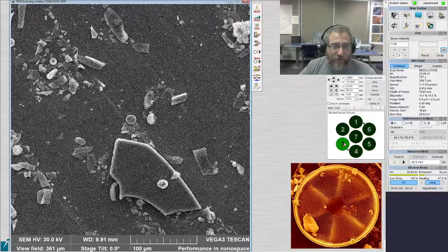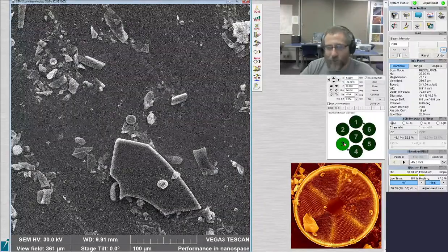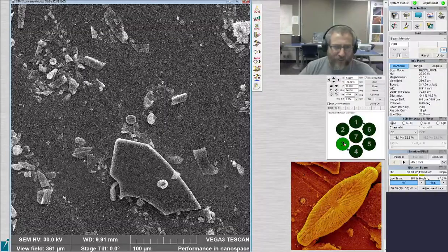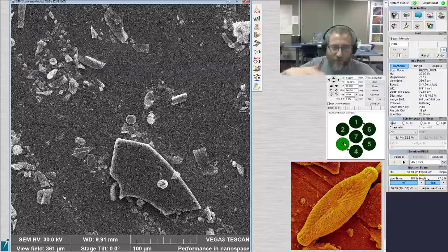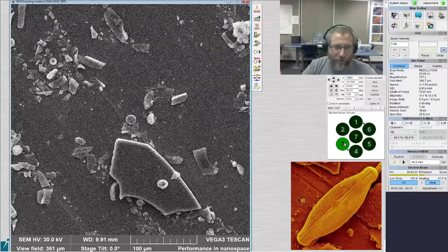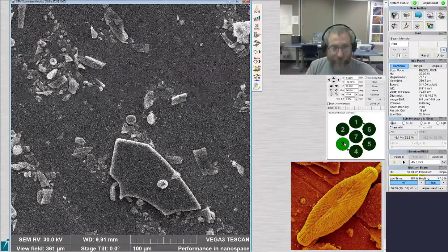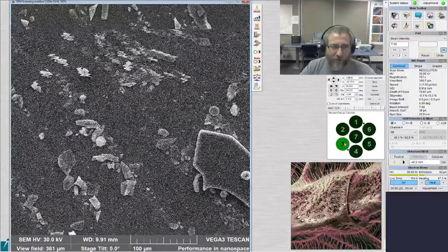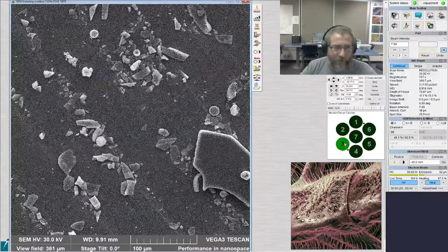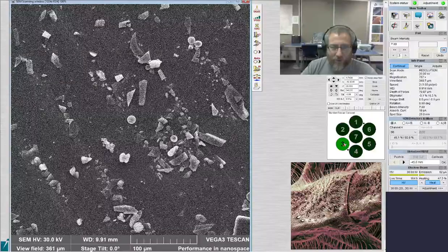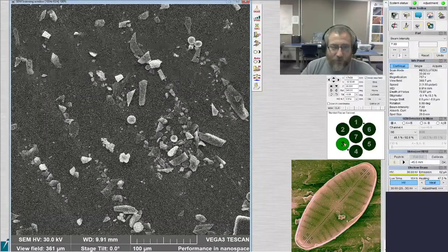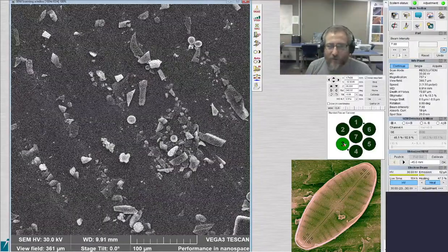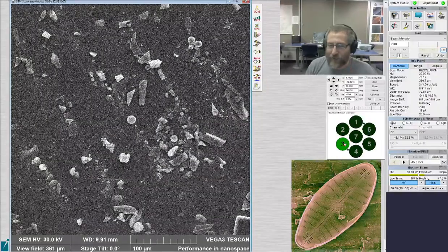Yeah, in a scanning electron microscope, it's sort of like, if you know what a stereoscopic normal microscope is that uses light, a scanning electron microscope is sort of like that. You have incident light coming from the top, it hits the surface, and then it creates a topographic or three-dimensional image that you can focus on the surface. And in the case of the scanning electron microscope, you can actually see a little bit into the subsurface, but not very far. A transmission electron microscope functions more like a standard upright transmission light microscope. In other words, the electrons pass all the way through, and the sensors are on the other side of it. So think of it sort of like you're seeing an X-ray of the material rather than seeing the surface.